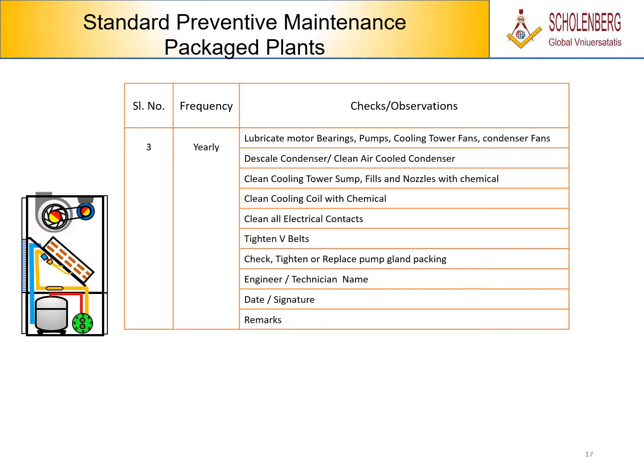Serial number 3. Frequency: yearly. Lubricate motor bearings, pumps, cooling tower fans, condenser fans. Descale condenser, clean air-cooled condenser. Clean cooling tower sump, fills and nozzles with chemical. Clean cooling coil with chemical. Clean all electrical contacts. Tighten V-belts. Check, tighten or replace pump gland packing. Engineer, technician name, date, signature. Remarks.